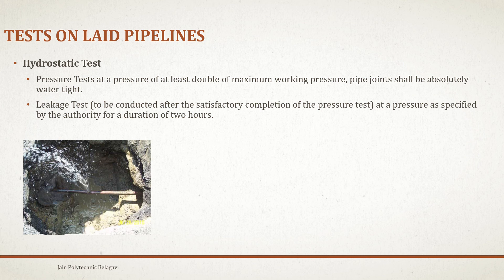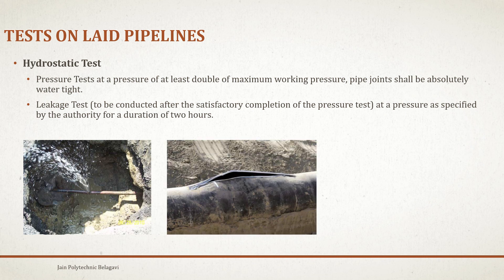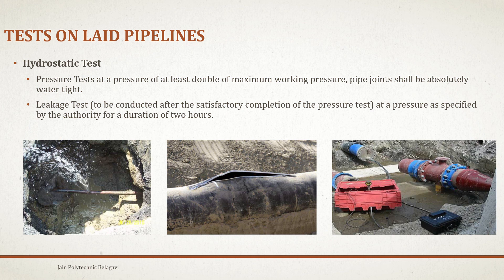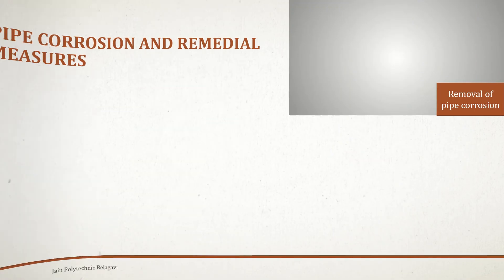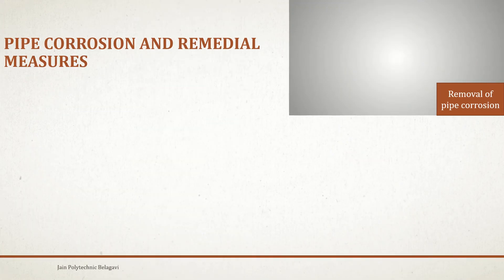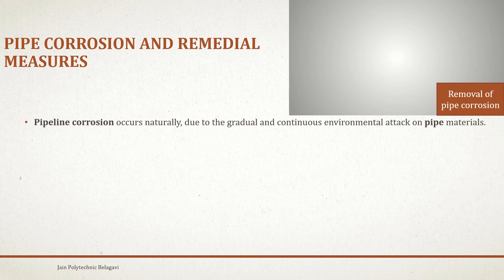After the two-hour checkup, if it is a hydrostatic test, the joint might get cracked and water starts flowing outside. This is what happens during the hydrostatic test. They were checking the pressure test — the pipe has been cut — and this is the hydrostatic test apparatus showing how they are going to conduct the test.